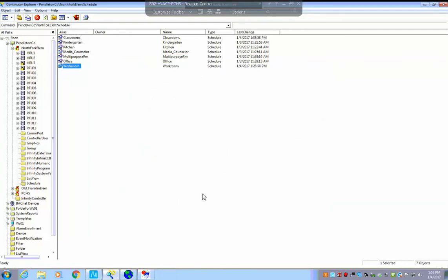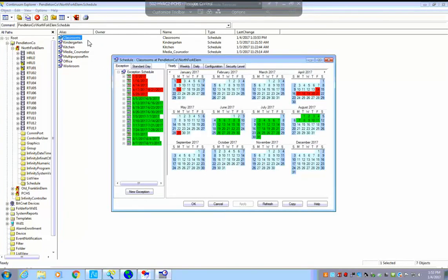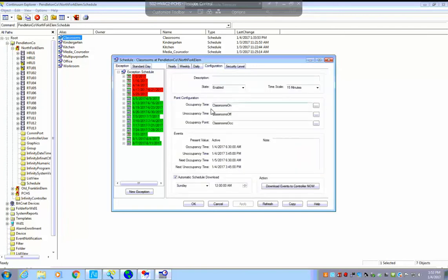So we'll cancel that one, or just okay that. Say you have a master schedule. We'll use the classroom as our master schedule. After you go through and set all the holidays throughout your year, as this person has done on this school for the classroom schedule, I guess they've not completed the rest of the year. Maybe they don't have it for September, because our school year ends on July 1st, so they probably didn't know what the holidays were after that. So anyway, this controls a separate set of points: classroom off, occupied, classrooms on, classrooms off. Okay, this does not change when you do this mass update.